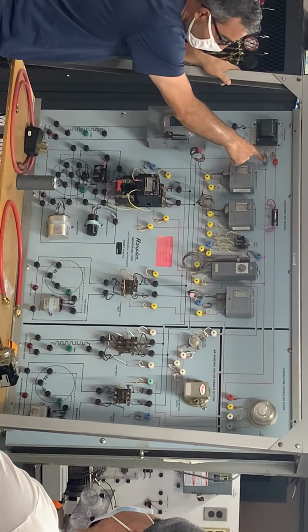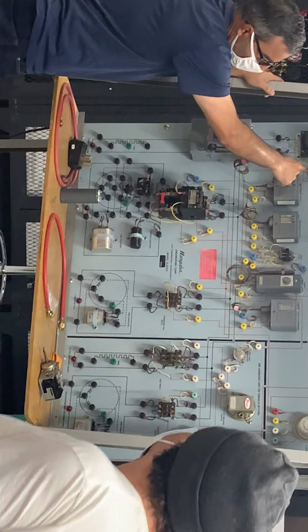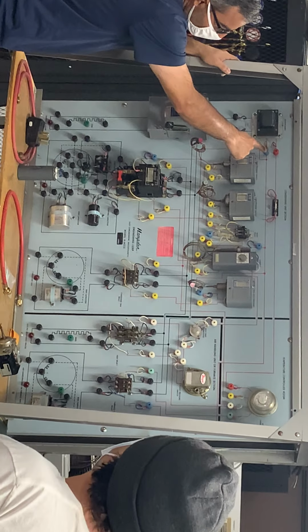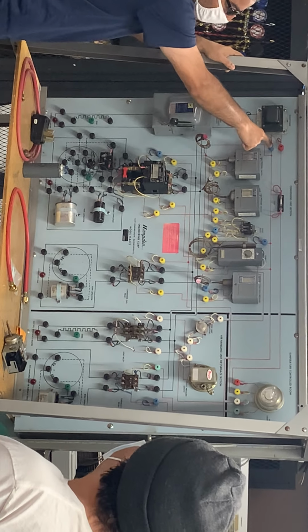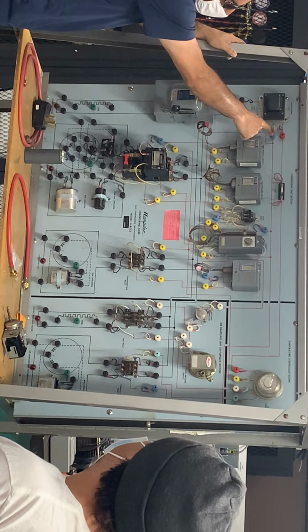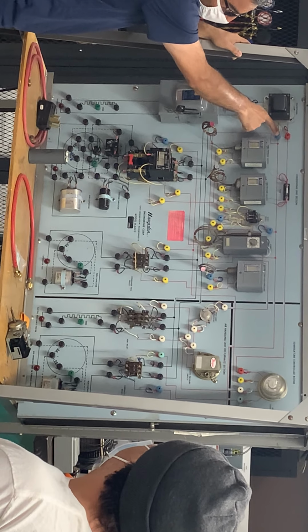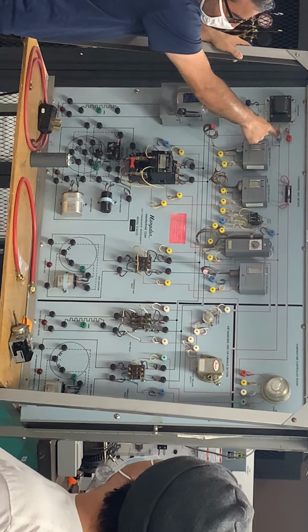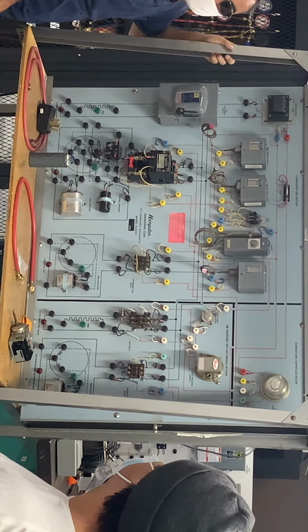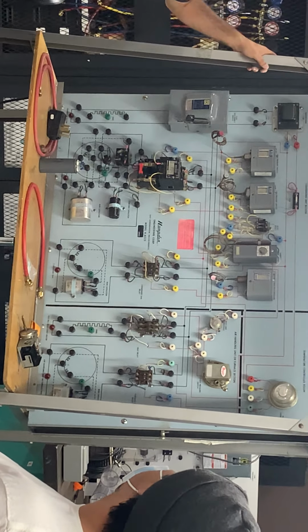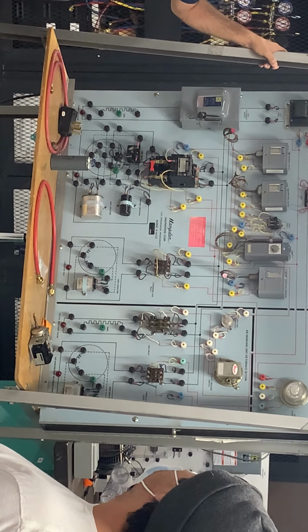So for the heater to work, of course the transformer has to be good, and the fuse has to be good. The thermostat switch from red to white has to close. Then we have a static pressure switch, a high limit thermostat, and that gray box with the knob, called an ambient thermostat. All of those have to be in the right position.